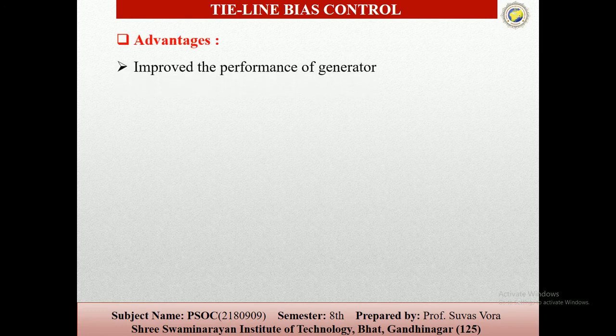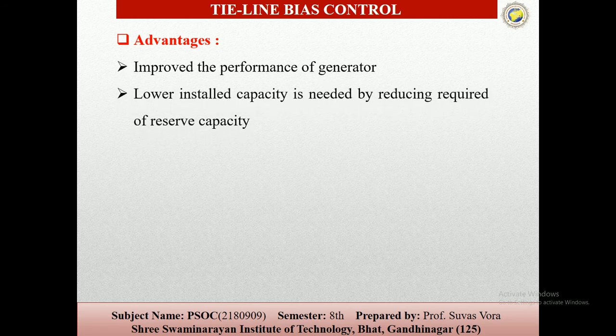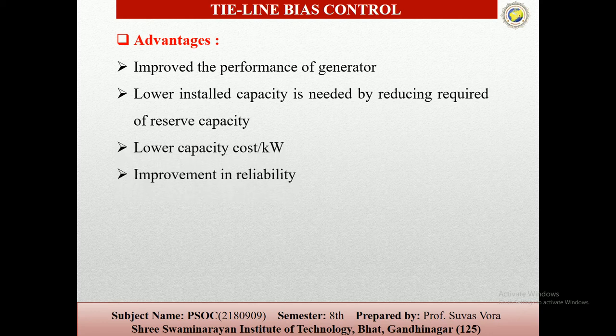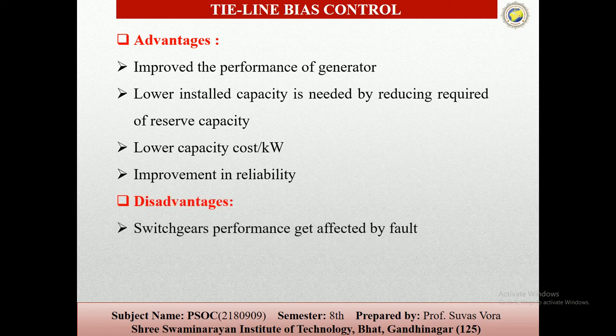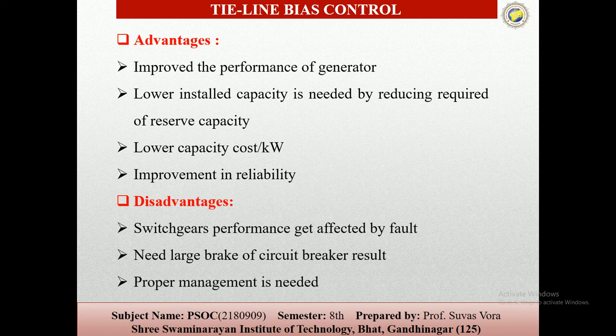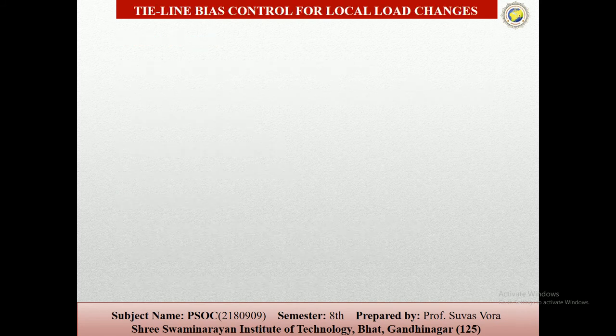The advantages of this system are to improve the performance of the generators, lower installed capacity needed by reducing the required reserve capacities, lower capacity cost, and improvement in reliability. What is the disadvantage? The switchgear performance gets affected by the faults, which needs large breaking capacity of the circuit breakers. Then proper management is needed.